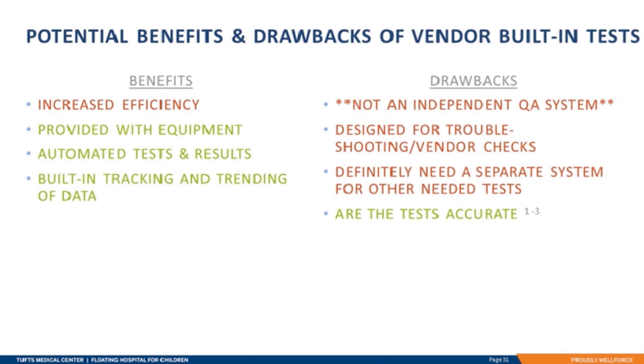Now let's come back to our benefits and drawbacks list from the beginning of the talk. From our analysis of these platforms, we have seen that while machine performance check can be performed quickly and the results are consistent with an independent system for the most part, the efficiency comes with a lack of sufficient tests to fully comply with the recommendations of TG-142. This means that while machine performance check could theoretically perform a subset of the daily QA tests, a separate system would be needed to record results from the remaining tests as well as provide documentation of review and approvals.